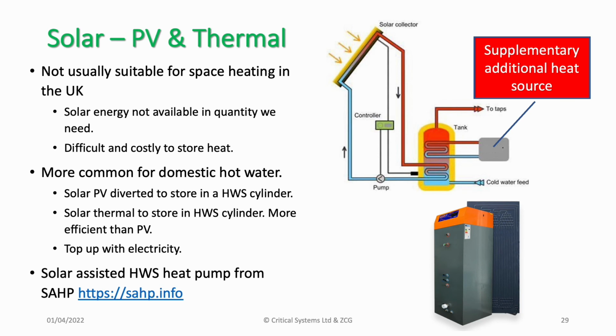We could also look at, and I saw recently from the firm I've illustrated here, a solar assisted heat pump. So this is a domestic hot water oriented system using a heat pump with an external solar panel through which the refrigerant flows, so it gets a high temperature external heat source. And this can operate as a high temperature heat pump for domestic hot water uses.